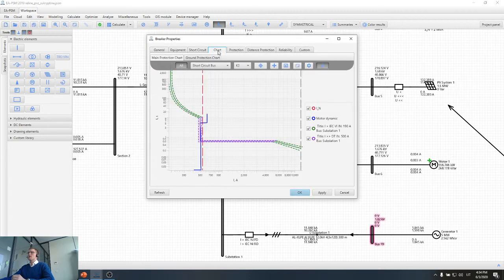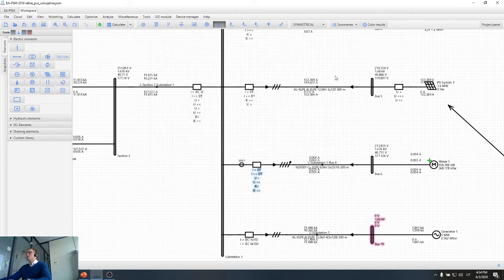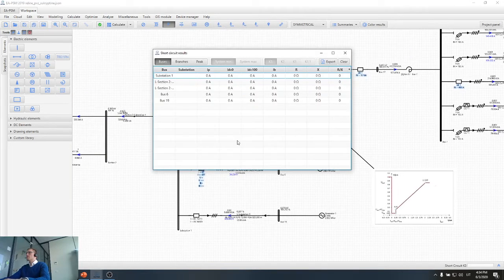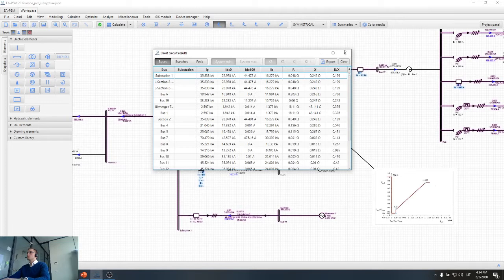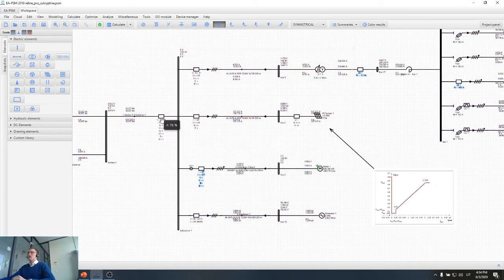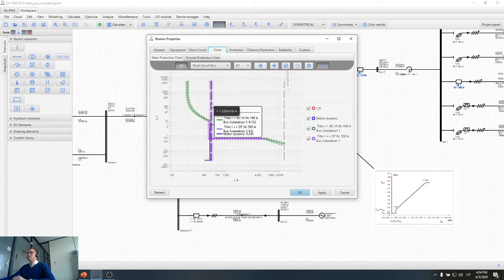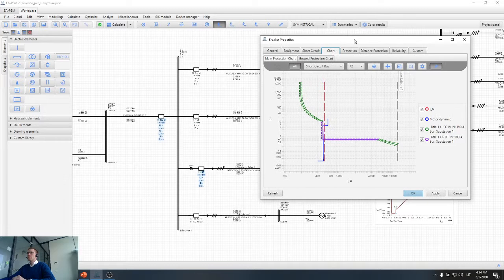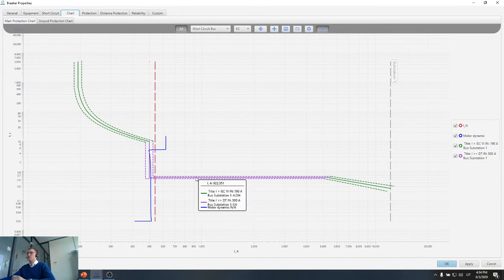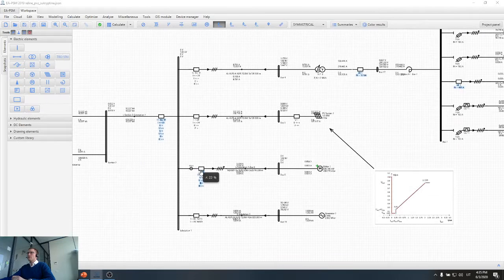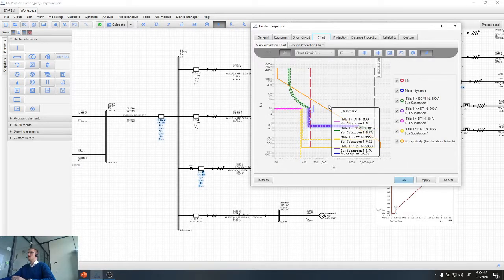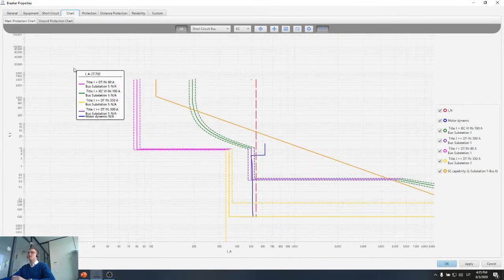Now let's check the selectivity coordination of this relay with the main incomer relay. I will double click on the main incomer relay, recalculate the short circuits and also load flows, and here I will open the setting. Okay, so we can see the current TCC curve of the main incomer device. What we have to do is add the motor relay in the same picture to see whether these two relays are selective.